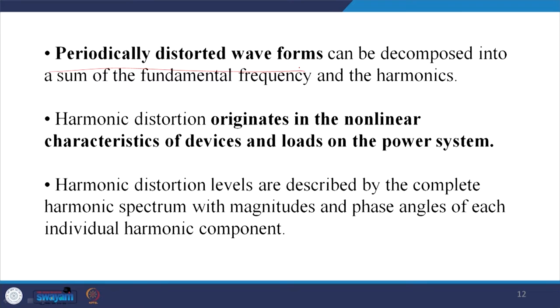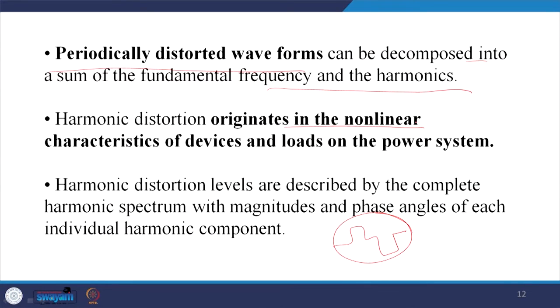A periodically distorted waveform can be decomposed into the sum of the fundamental frequency and harmonics. For example, a square waveform — which is a distorted sine waveform — can be split into sine and cosine components with corresponding harmonics in a Fourier series. Harmonic distortion originates in the non-linear characteristics of devices and loads on the power system: diode-based rectifiers, thyristors, and AC-to-DC converters all cause harmonic distortion.